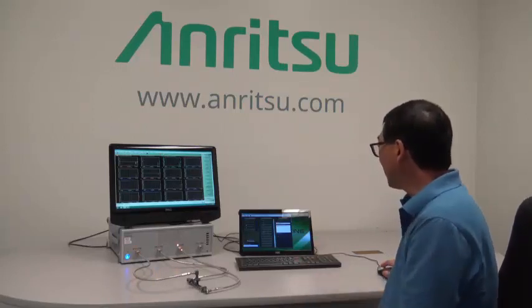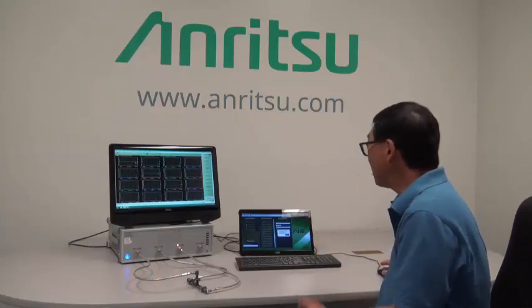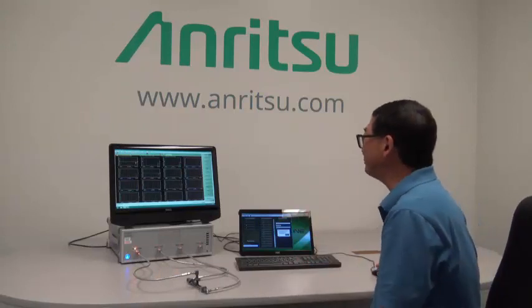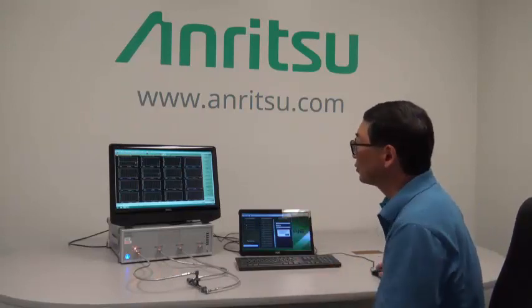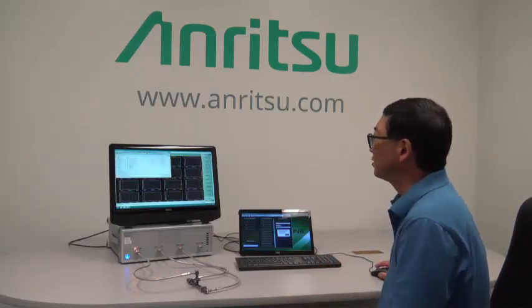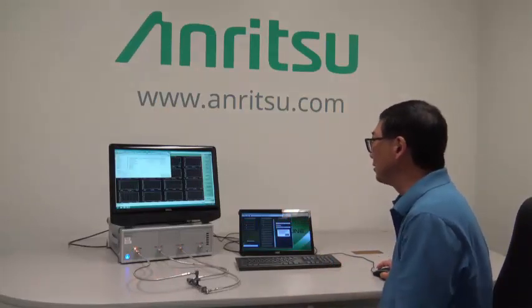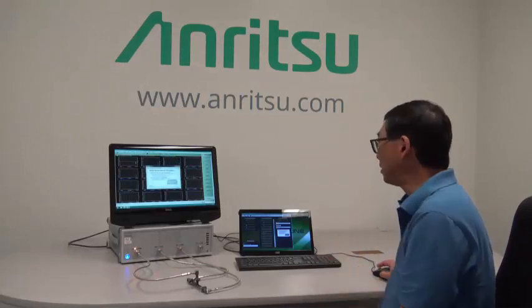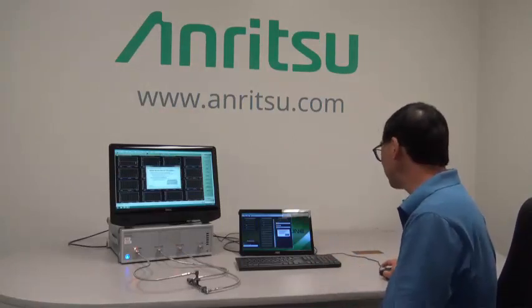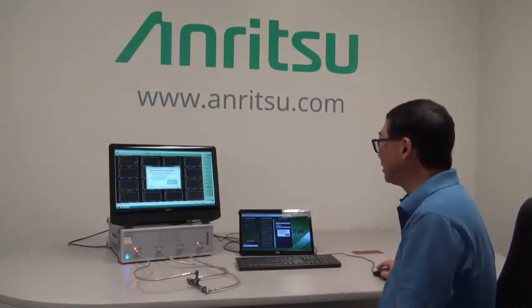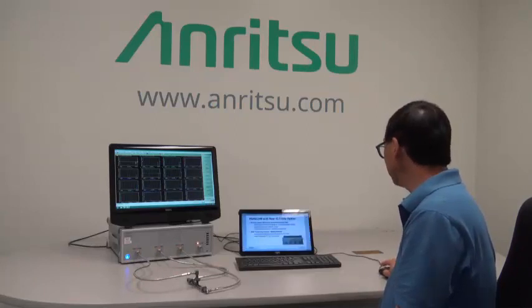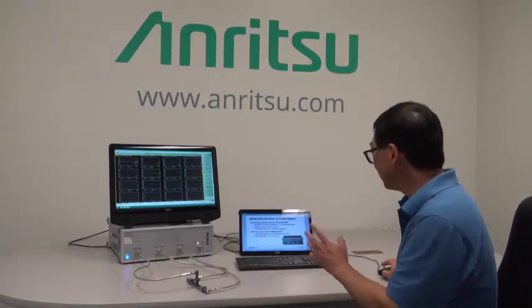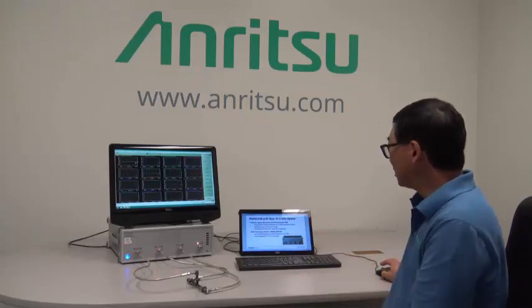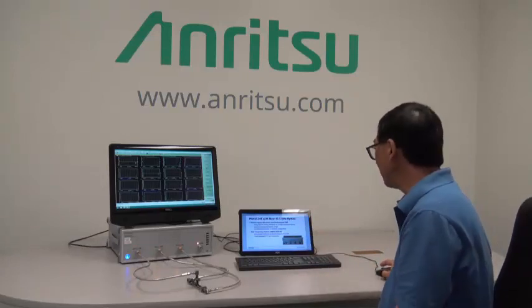And let's take a look at how this operates on the software itself. In the ShockLine software, we have an easyTest function which executes the file that we've written over here. So you can see the graphic here matches the graphic over here. Let's move this over to the other screen and pin it in place so that it doesn't move, and we can go through the different steps in this sequence.